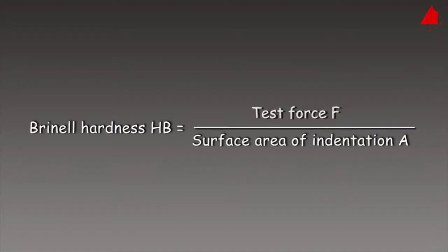That's it! The testing machine can now calculate the Brinell hardness. The hardness value is defined as test force F in the old unit kilopond divided by the area of the indentation A in square millimeters.